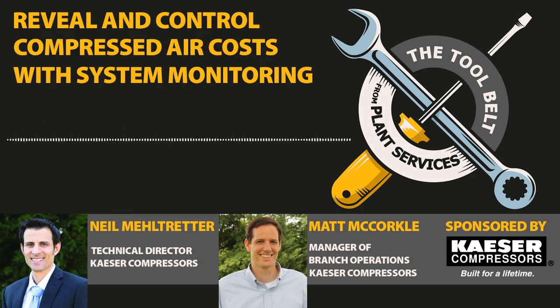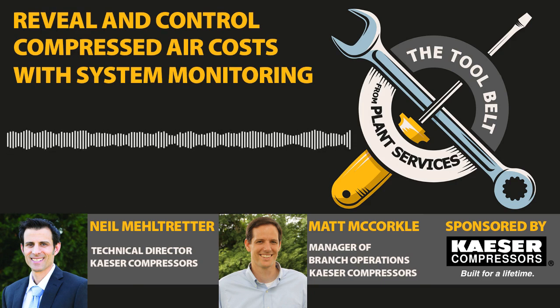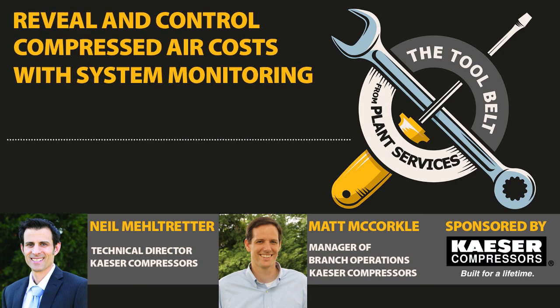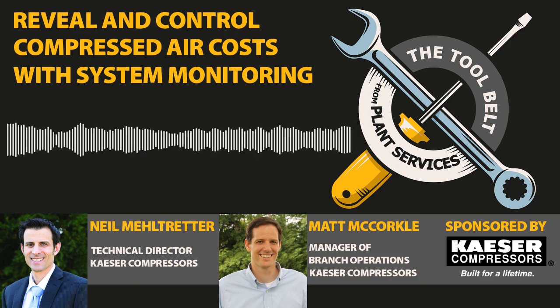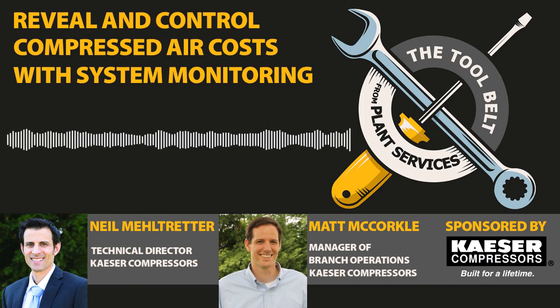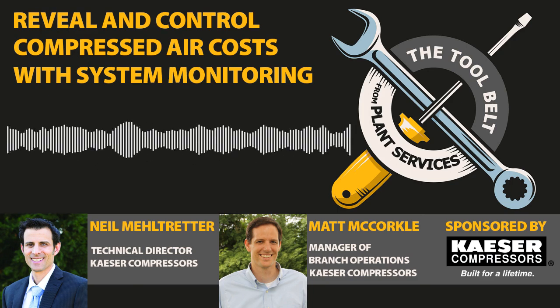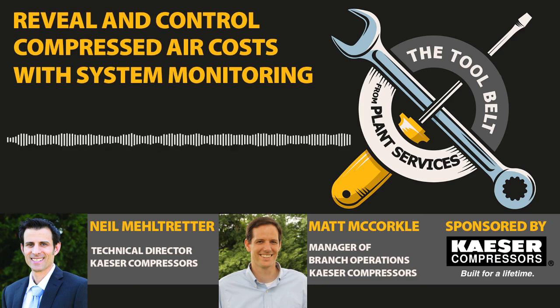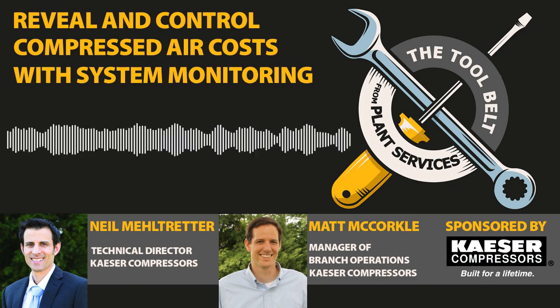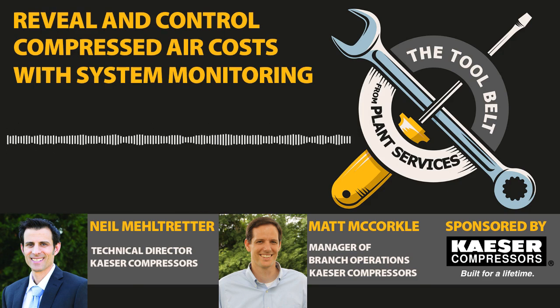And then in terms of a quarterly basis or possibly monthly basis, looking at your overall consumption and costs. So when you're looking at your consumption profiles, really seeing, have maybe different operators, are they operating equipment differently, causing higher costs than other operators? Are different production lines, is their consumption changing, or different products costing you more in air? So that's something that can be done on a more periodic basis. But those are the things I would check. And I think, with the master control, it enables even the busiest of folks to be able to check that, stay on top of it, and really minimize those hidden costs.